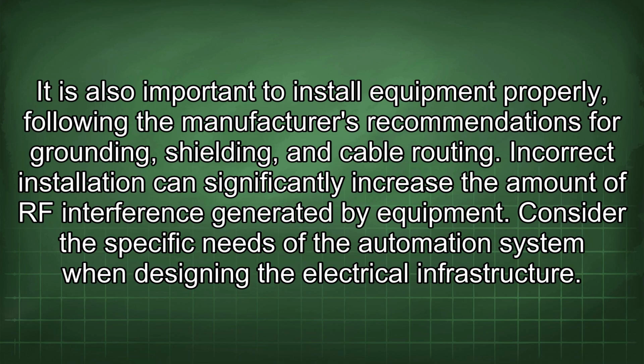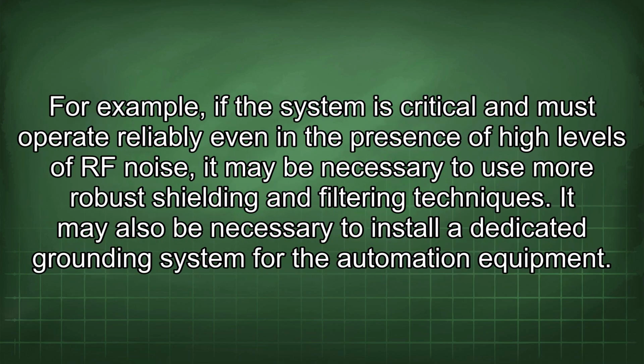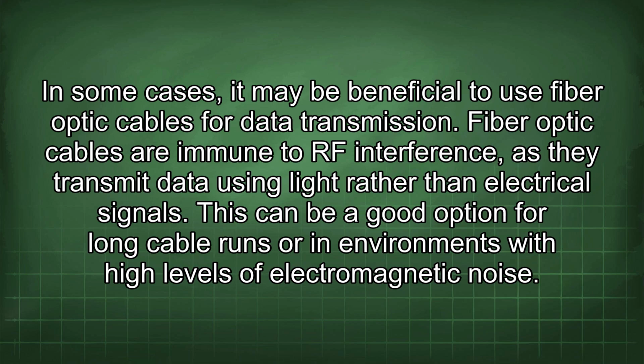Consider the specific needs of the automation system when designing the electrical infrastructure. For example, if the system is critical and must operate reliably even in the presence of high levels of RF noise, it may be necessary to use more robust shielding and filtering techniques. It may also be necessary to install a dedicated grounding system for the automation equipment. In some cases, it may be beneficial to use fiber optic cables for data transmission. Fiber optic cables are immune to RF interference, as they transmit data using light rather than electrical signals. This can be a good option for long cable runs or in environments with high levels of electromagnetic noise.